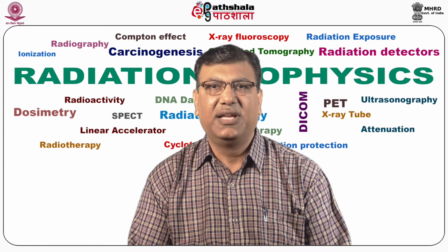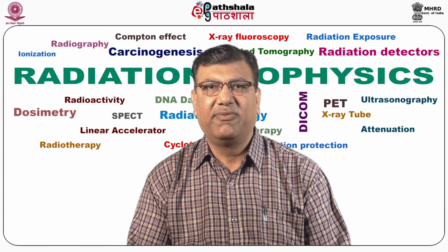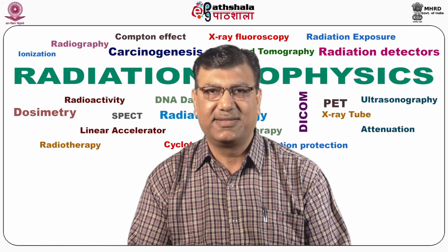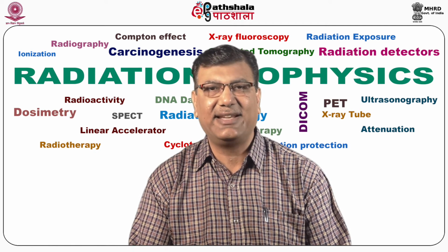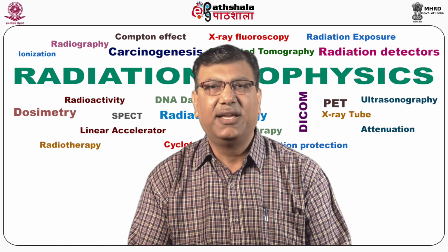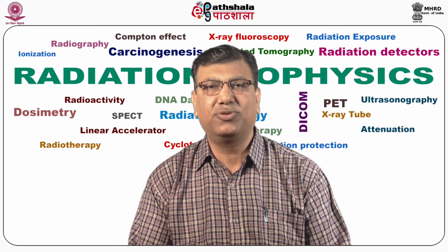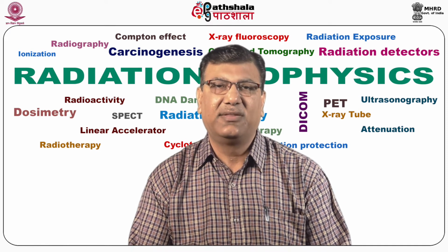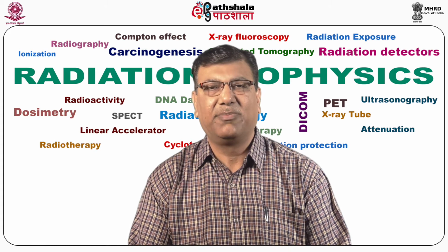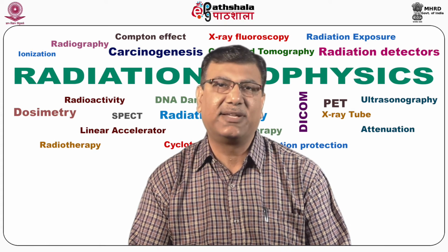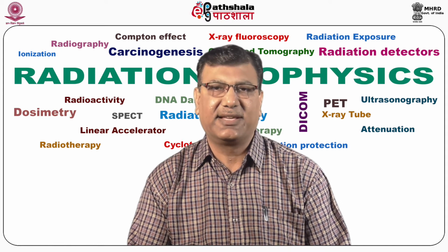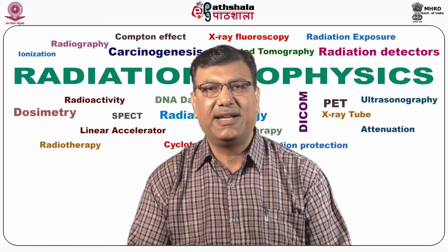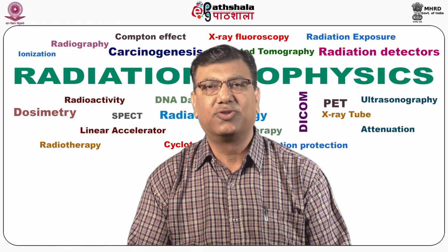In the introduction, external beam radiotherapy is where the source of radiation is outside the body and at some distance. The distance generally is 80 centimeters to 100 centimeters. In teletherapy machines, most of which use a cobalt-60 radioactive source, the distance from source to patient is approximately 80 centimeters.